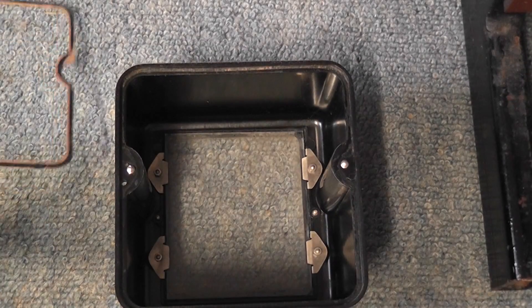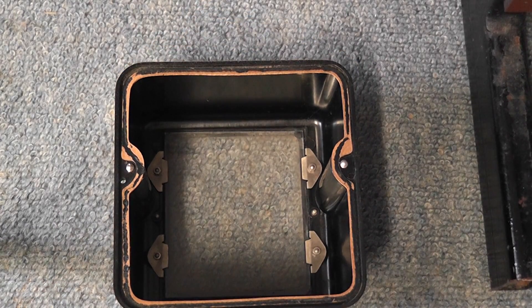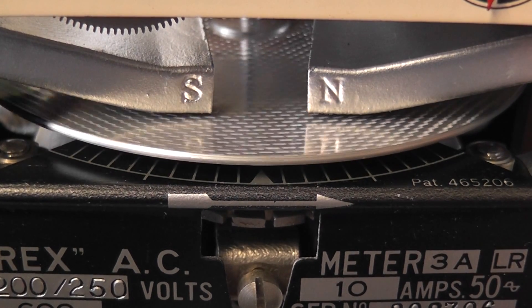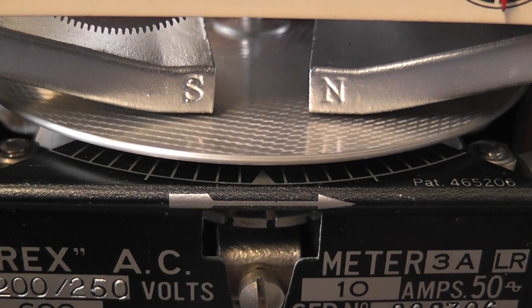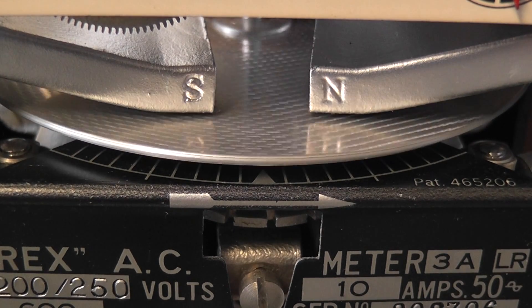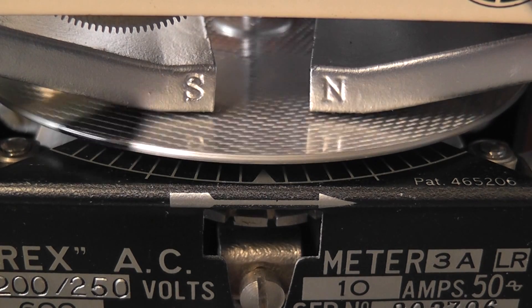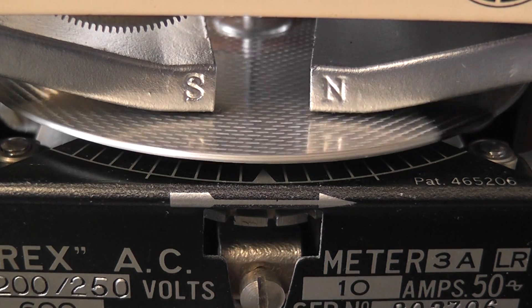This is the cover and it had a nice dry gasket in here that sits around the rim. The thing I just noticed on the meter, which is quite amazing for calibration — have a look at this. That's actually a graduated calibration scale underneath the disc. I've never seen that on a meter before. So if you stop the disc here at the right moment and adjust the load, you can do a start-stop test. It's quite cool to see a graduation disc underneath the meter accuracy disc — it's just engineering at its best.